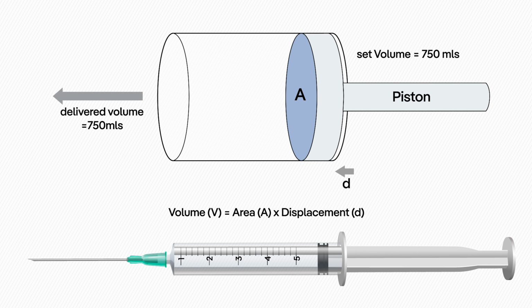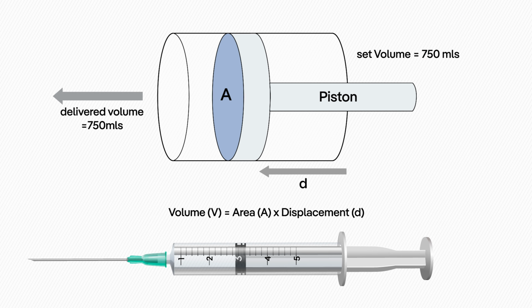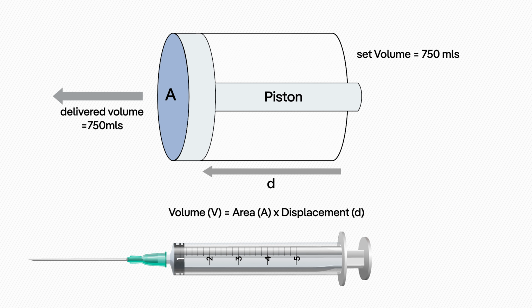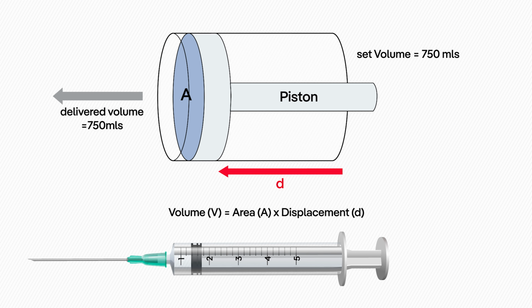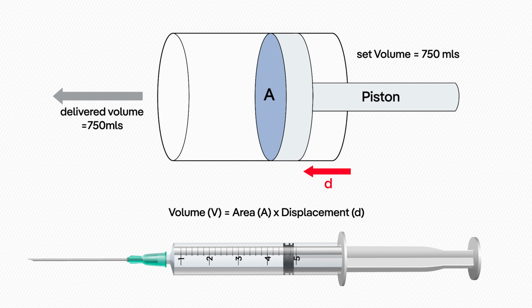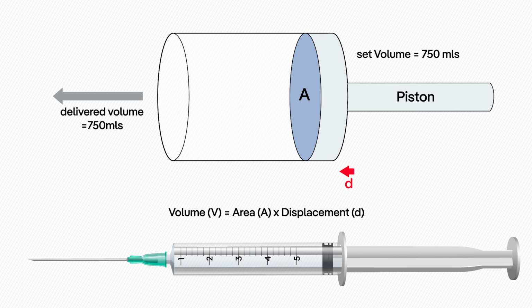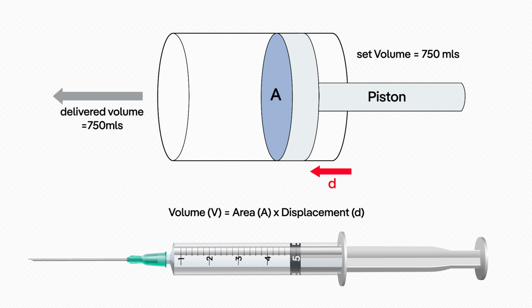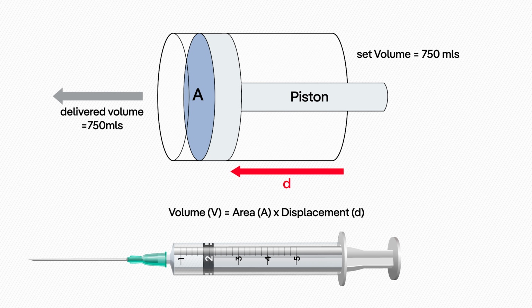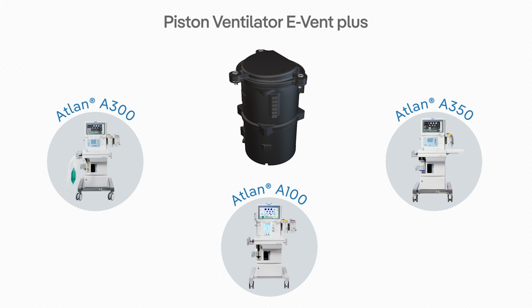Even in the unlikely case of a flow sensor failure, via the stepper motor moving the piston, the ventilator always knows the piston's position to calculate the tidal volume to be delivered. Therefore, the functionality of the piston ventilator is independent of flow measurement. The piston ventilator in Atlan family is designed to deliver precise tidal volumes.